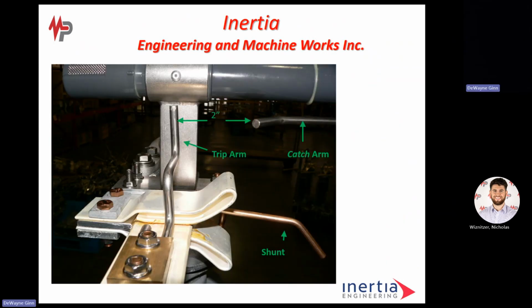So from that phase unit we looked at a while ago, up top here is that interrupter. Inside that interrupter, again, is a white probe. It comes out of a load break elbow. If you ever looked inside or saw a load break elbow, it's the same white probe inside of that. When it makes and breaks the full load break, it's got orange quenching material. It's going to be excited gases when I break that circuit. In the back here, you see some vents, and you'll have a little smoke come out of those vents. That's common, because it's extinguishing those high energy gases at that point. So it's just extinguishing gas. Sometimes you'll hear this interrupter called a puffer, just because of the smoke that comes out of it.